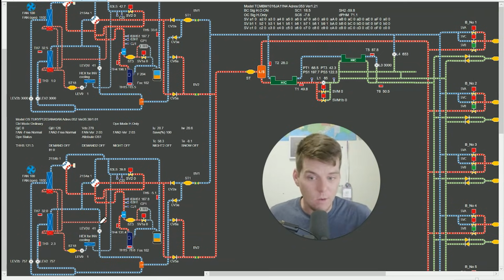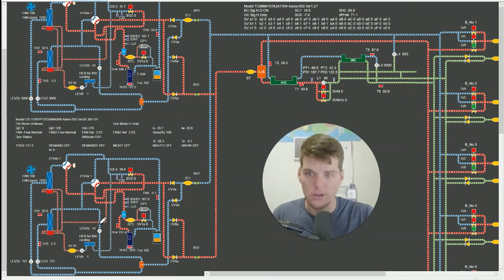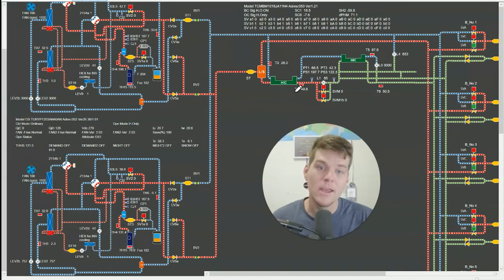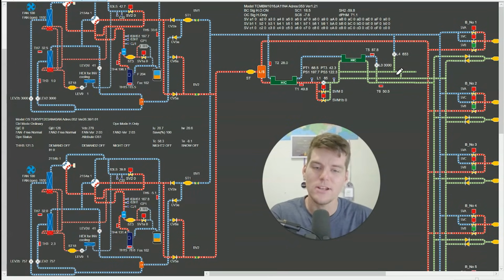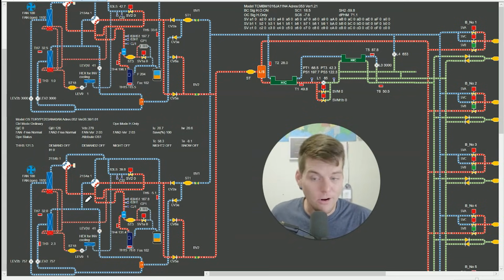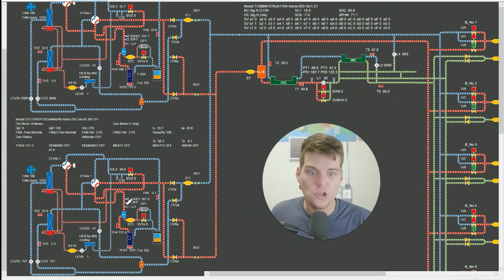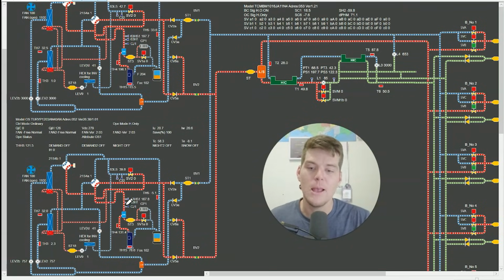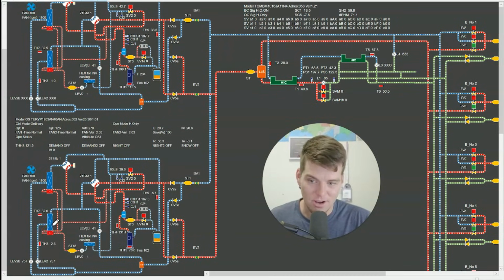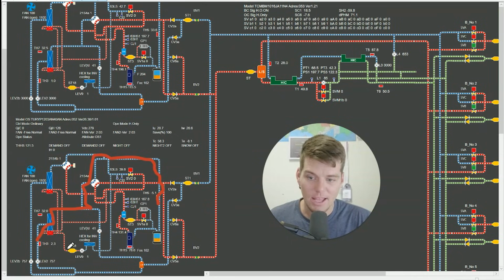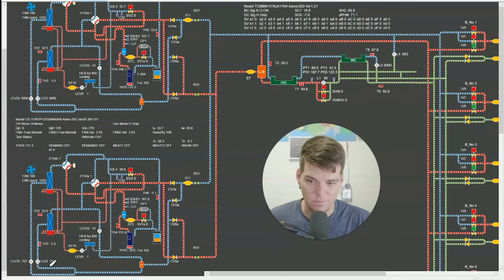Now my system looks like what? Well, it looks like low charge, but not everywhere. It looks like low charge on the master module where there is no problem. It looks like low charge on all the indoor units and the branch collector box. However, the sub module, where it's stacked so much liquid that it doesn't know what to do with it, is literally flooding on the lower heat exchanger. Look at the superheat. We're coming up across here and we're coming back here. It's 2.3 degrees and now it's negative 5.2.